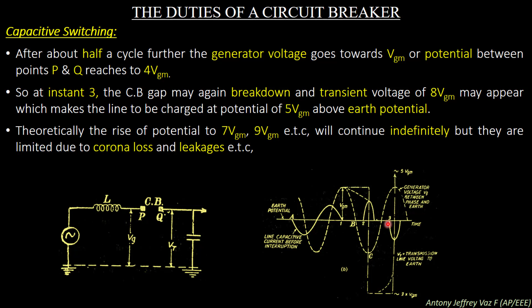This can be stopped only if the circuit breaker dielectric strength regains at a faster rate, so that the gap's dielectric strength is very high. A circuit breaker employed for a particular application should be capable of performing opening and closing operations without getting damaged due to overvoltage within specific limits. So the circuit breakers which are designed should be able to perform this capacitive switching for a short period of time without damage, and this capacitive switching has some limits. When these limits are exceeded, the circuit breaker gets damaged.